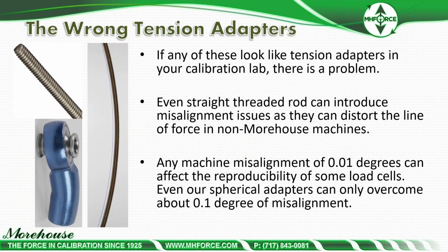But the wrong adapters, hey, I've been in this 21 years now, and coming in in 1999, I saw some threaded rods still being used way back then. Fortunately, we got rid of that pretty quickly. You could tell if you had a bad piece of threaded rod: you rotate a load cell, and the results don't come into alignment. They're actually bad.